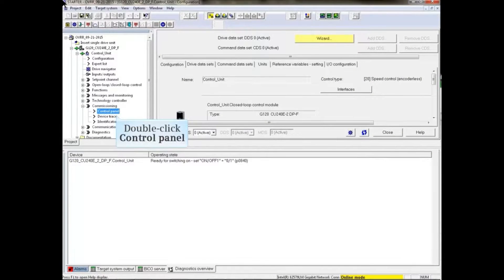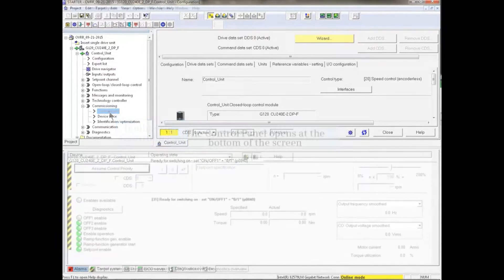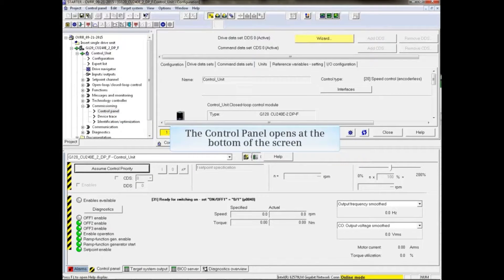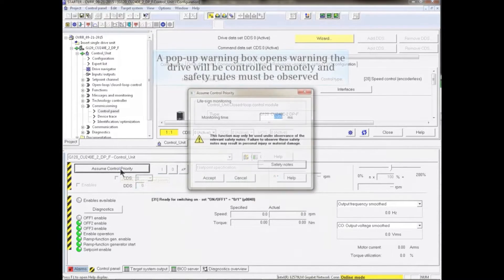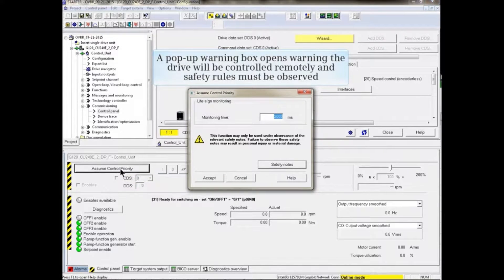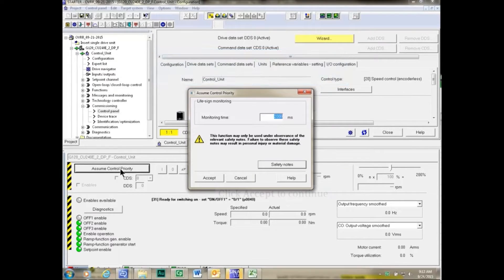Online with the drive, double-click the control panel listing under Commissioning in the project tree. The control panel opens at the bottom of the screen. Click the Assume Control Priority button. A pop-up warning box opens warning that the drive will be controlled remotely and safety rules must be observed. Click Accept to continue.